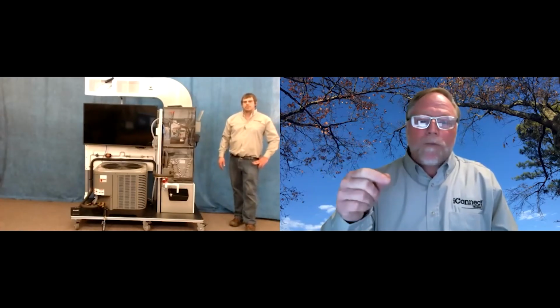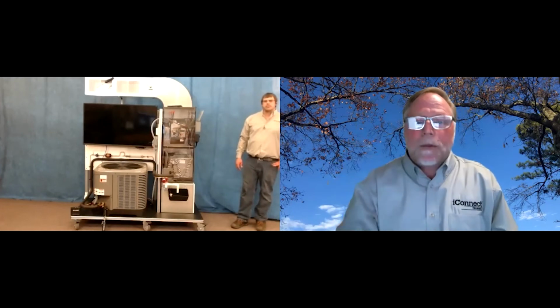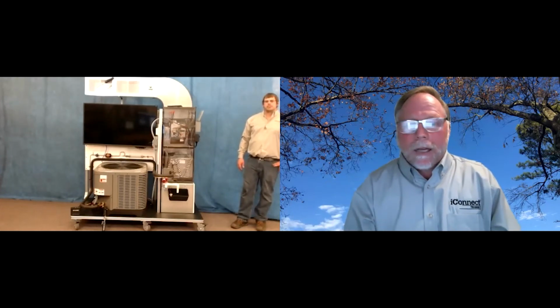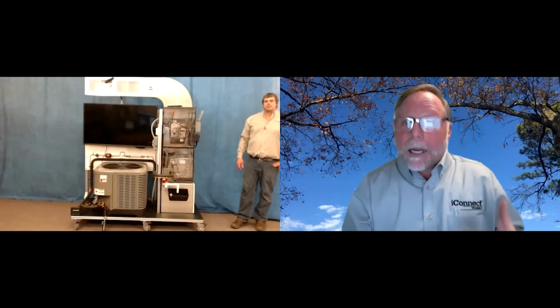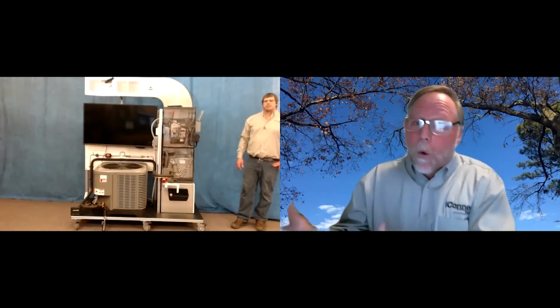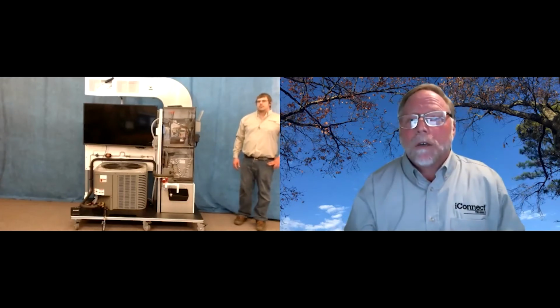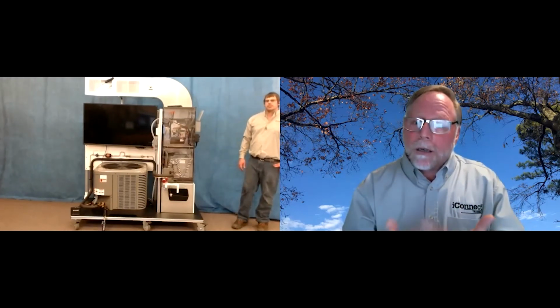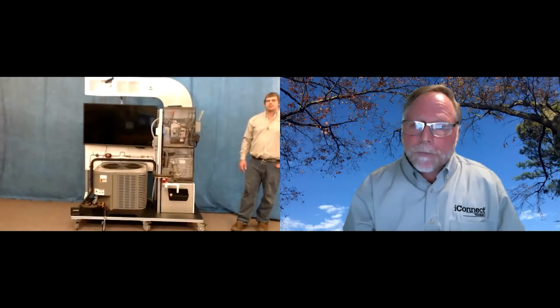So we pulled out that dirty filter, we've thrown in a clean filter, and look what happens. We get full airflow again, and you can see that pressure starting to rise and the temperature starting to rise. And why is that? That's because we're now moving warm air back across the evaporator coil, and we're moving the right quantity of air. Before we weren't, because we had a dirty filter. And that's what we just represented with lowering the airflow.